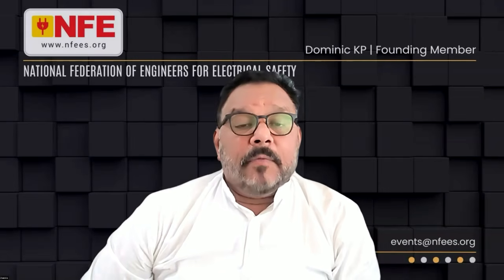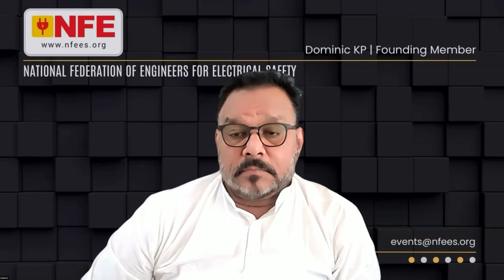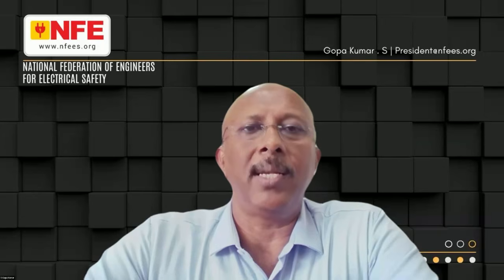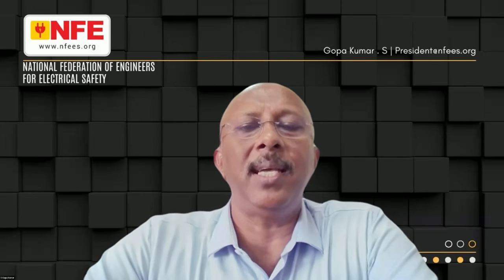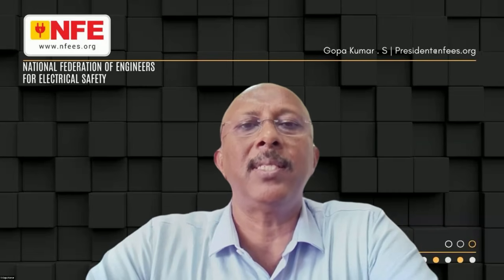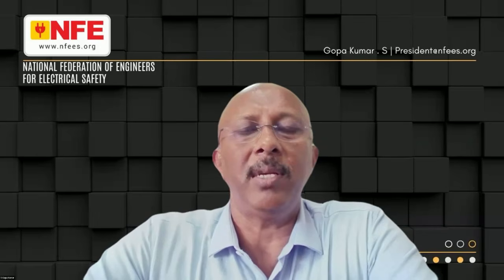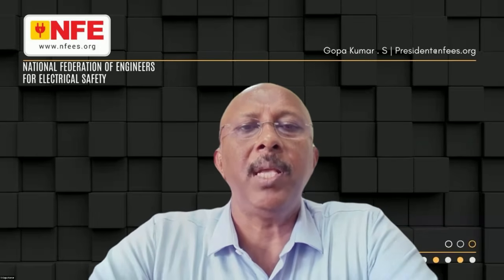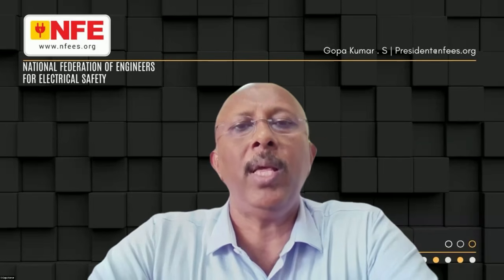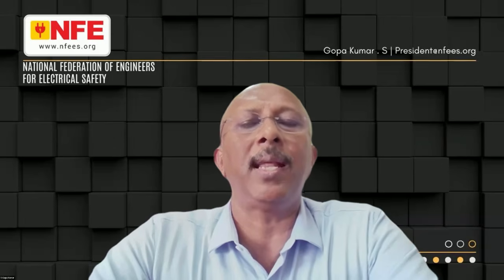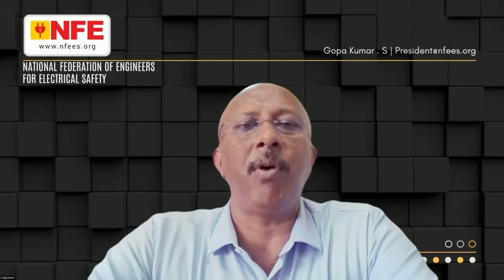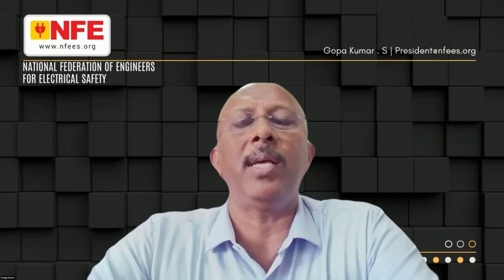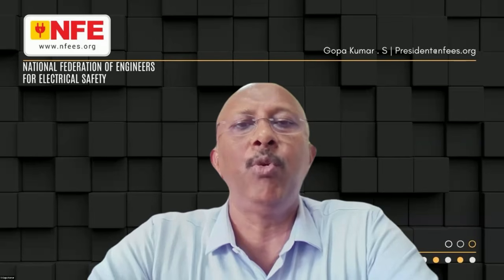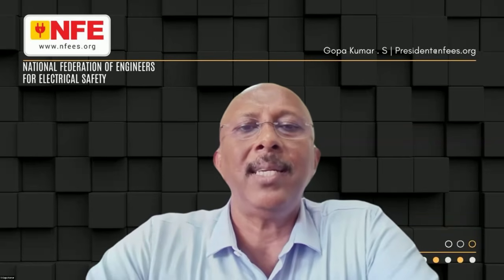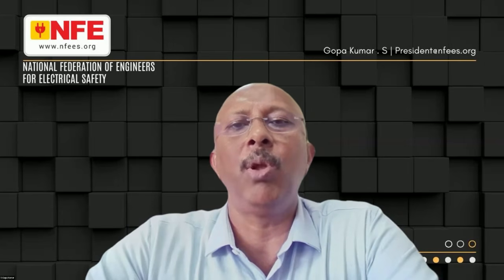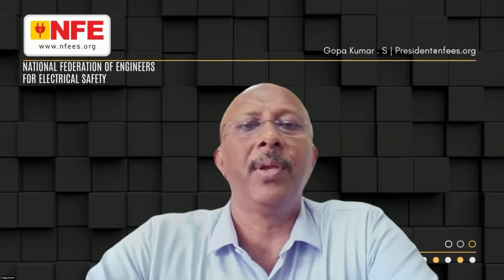There's one more question on the top. Urmil Vaidya is asking: is there any way to check loose connections in an electrical installation? Yes, Mr. Vaidya, that is the first test in the electrical installation, which is called the continuity resistance test. Continuity resistance means you have to have a micro ohm meter and you have to test the resistance of the wires, including the termination, before you use the electrical wiring. And you have to record it in the prescribed format. That is the first test. So it is not just a way to test. It is a mandatory requirement. Before you use electricity, you must check whether the resistance of the connections, including the resistance of the wires, is much lower than the values prescribed.